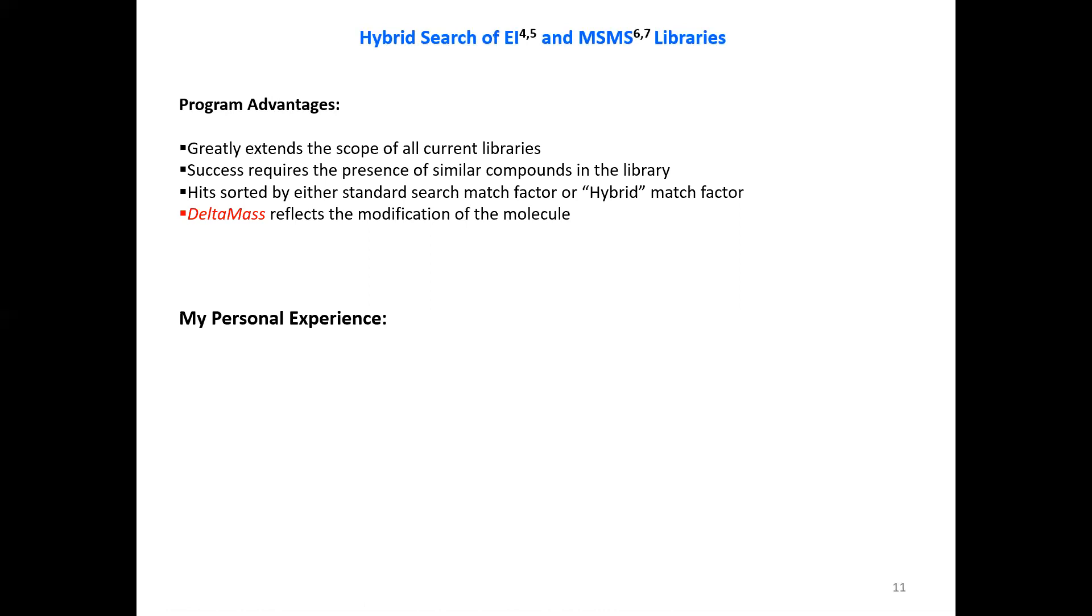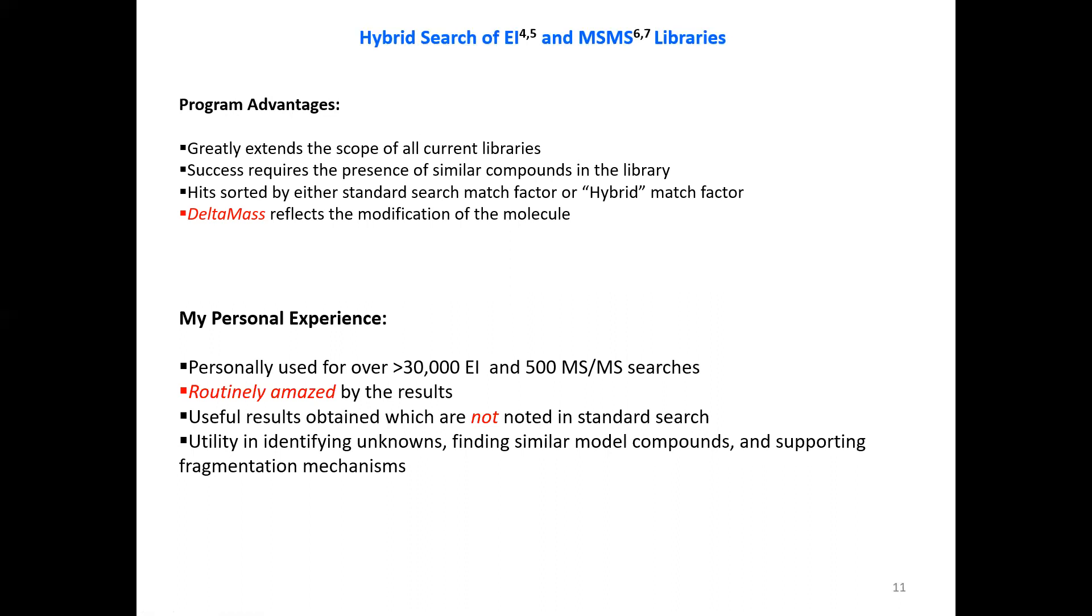My personal experience with the hybrid search, I've personally used it for over 30,000 EI searches and 500 MSMS searches. I'm routinely amazed by the results I get from it. Useful results are obtained which are not noted in a standard search. That's why it extends the scope of the libraries that one uses. Its utility is in identifying unknowns, finding similar model compounds, and supporting fragmentation mechanisms.